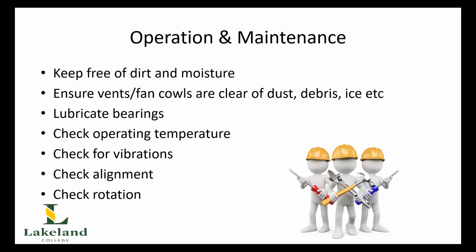If you allow the fan cowling to ice over, then we'll reduce the flow of air through them, and that will lead to overheating. So take your pipe wrench or your crescent wrench and just gently tap the fan cowling to remove the ice. And that's certainly something that you have to check on things like cooling towers, where there's a lot of water splashing around and water vapor moving around from the cooling tower.